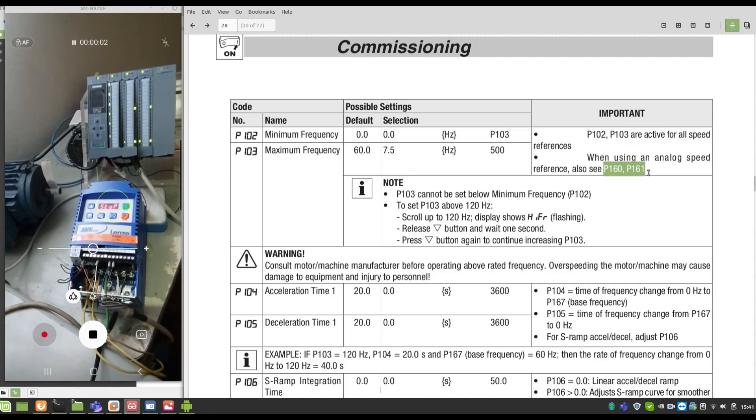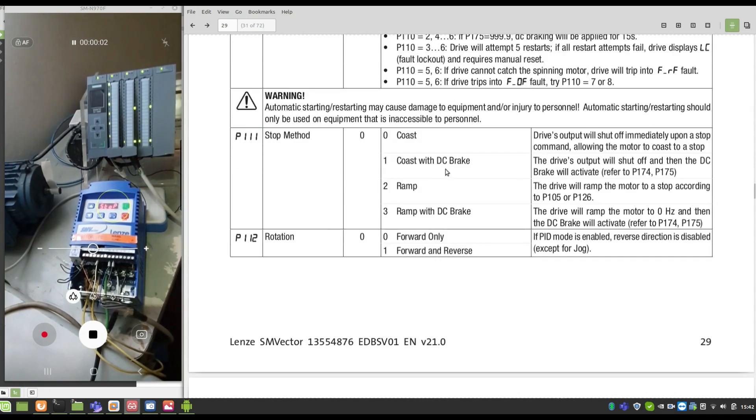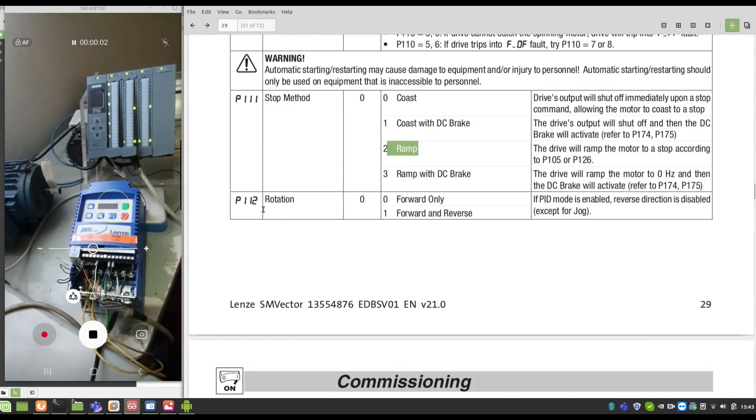We must set parameters P102 and P103 for minimum and maximum speed. Acceleration time is parameter P104, and the deceleration time is P105. Stop method — we can use inertial stop, which stops using the motor's inertia. We're going to parametrize it via deceleration ramps — P111, value 2. And P112 for rotation — forward and reverse — P112, value 1.